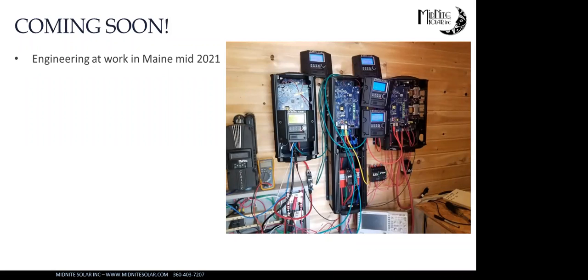When you send a kill signal to the charge controller by opening two wires, the system shuts down. So if you had a whole MidNite system, all systems would intertwine together. If you had just a Hawke's Bay, for example, you'll have a 2-wire circuit. You use your favorite lockable push button outside, and when you push that button and open that circuit, the rapid shutdown signal goes away and the system shuts down.